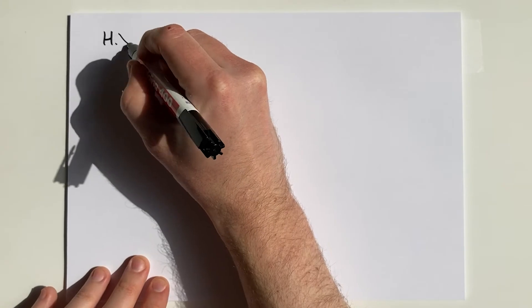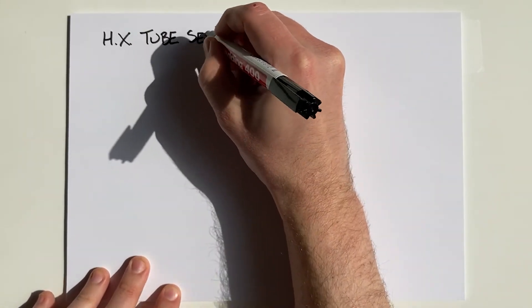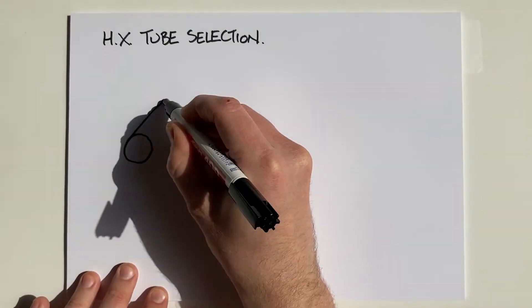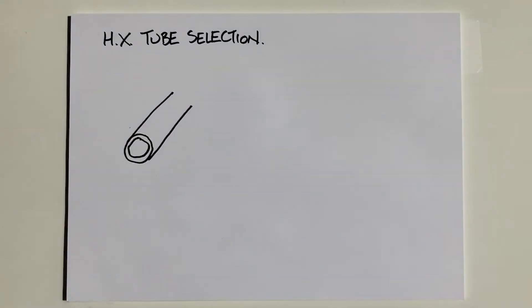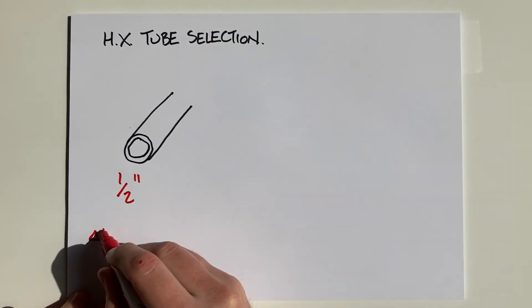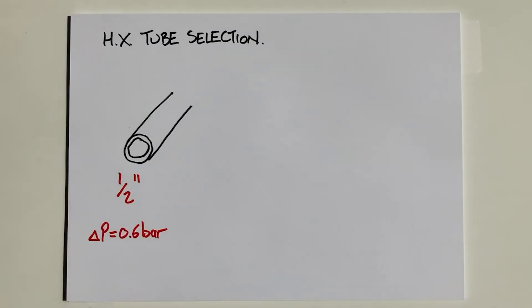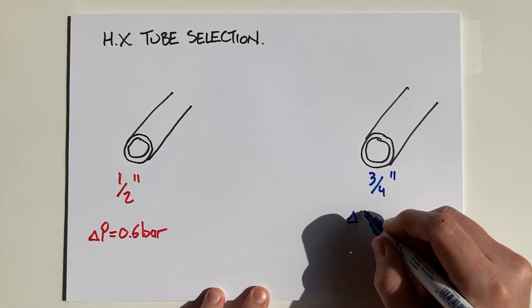So, you've accepted your half a bar worth of pressure drop for your heat exchanger. You set out to do the design and pick a tube size. Let's say you pick half inch tubes. You do the calculation and you see that the pressure drop for this heat exchanger will be 0.6 bar. That's more than your budget because your tubes are too small — the velocities are too high. You need larger tubes. So you pick the next standard size up: three quarter inch tubes, and you go through the process again and calculate that the pressure drop is now 0.4 bar.